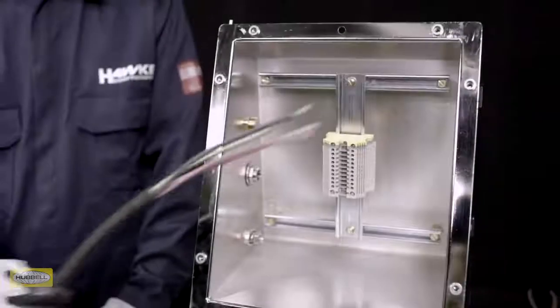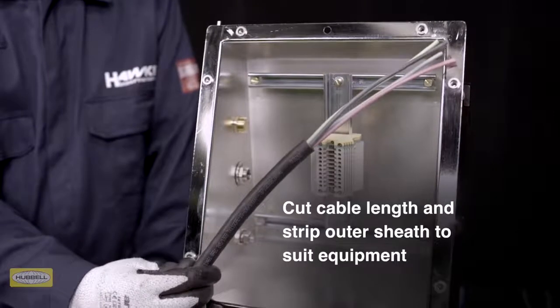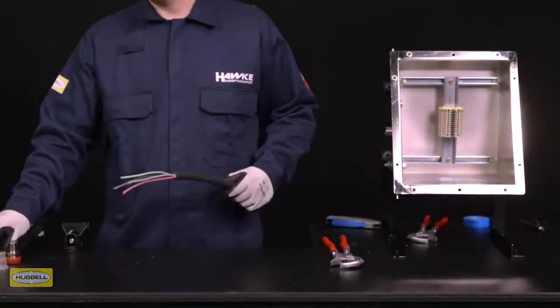Assembly instructions are provided with Hawke cable glands or can be downloaded from the Hawke website. Allow sufficient length of cable and strip the outer sheath to suit the equipment the cable is being terminated into. Slide the back nuts and middle nuts onto the cable.